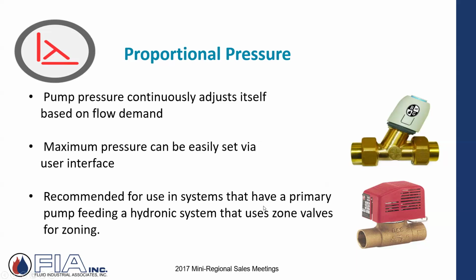So one very popular mode out in the apartment, condo, multiple zones with thermostats and a zone valve of some sort is a mode called proportional pressure. And all it's saying is I've got this one distribution pump that's feeding 30 apartments, 50 apartments, coils, baseboard, whatever they are. And same thing as we just talked about with the variable speed in those larger applications, this is a variable speed application. As those zones, as those loads change, valves open and close, the pump can respond accordingly.